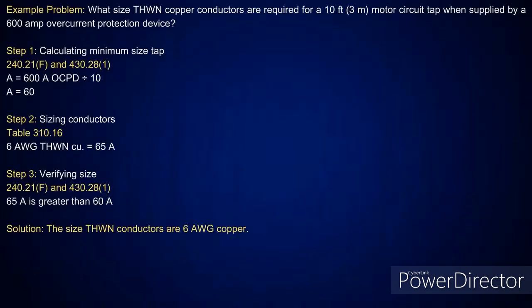Now, let's look at this. Here's a motor circuit tap. Now, looky there. It's 10 foot. If it's 10 foot, what do I divide it by? Divide by 10. See, I never changed anything. 10 foot or less, divide by 10. See, we give you a lot of different things in here. We may say boom, boom, boom, boom. Then we throw a little sidetrack in there. Here's one for a motor, 10 foot or less. How do you do it? Same thing like we did earlier.